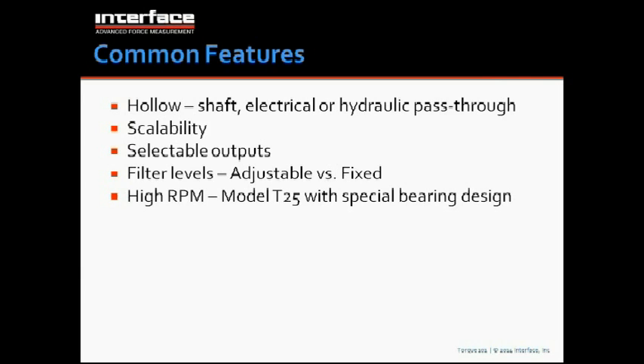Filter levels, again, data acquisition, you can do filtering, but in some cases people want the signal to be less noisy coming straight out of the sensor. Therefore, you want some filtering in the sensor. If those filters are adjustable, that can be handy. If they're fixed, it's important to understand what they are and what the limitations may be.